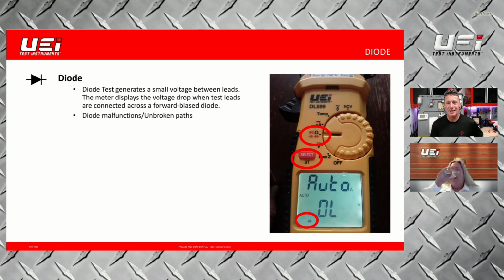I like how you've added all of the components that should not have voltage applied to them into the one key tab, so it gets all of them isolated. Everything else, we could have voltage applied. The tool itself is going to be generating its small amount of voltage that's going to be used for test purposes, so we have to make sure that anything we're doing in this function, any of those four components, needs to be done with power off on our control circuit. Excellent observation, yeah, very cool.